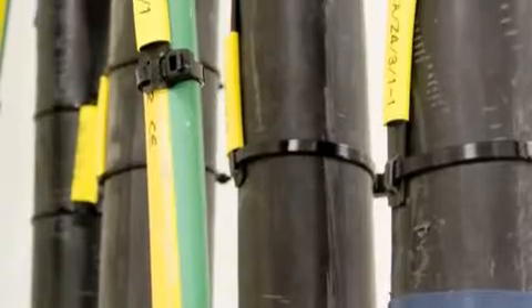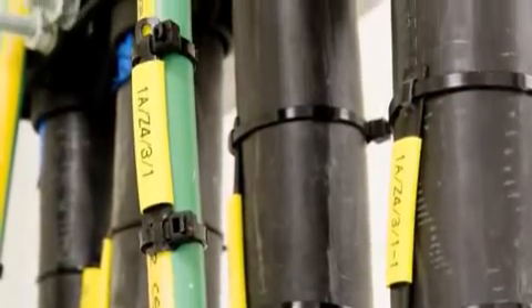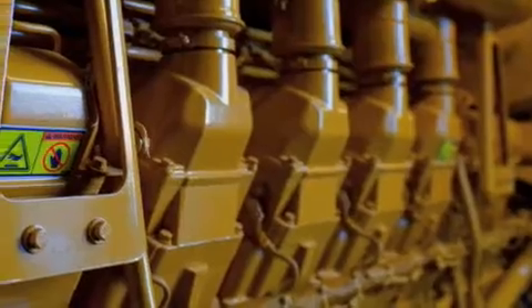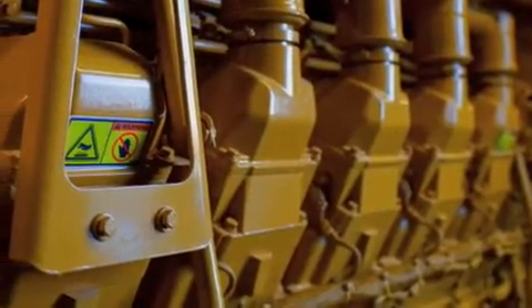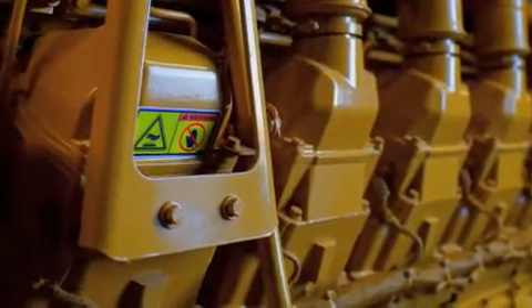We have diverse power feeds to site, 2 25 MVA feeds. In the unlikely event that we do have a mains failure, we have 12 2-megawatt generators. These generators are constantly warmed and can come up to speed in a matter of seconds to support the site. So the generators are supplied by diverse fuel tanks. Each one of the fuel tanks is capable of delivering 48 hours at full design load.